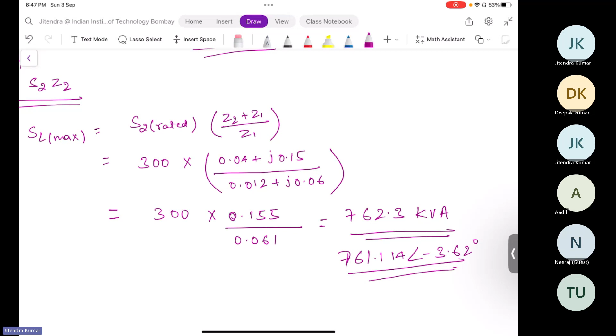If we exceed this value, then one transformer will get overloaded. Yeah, you are perfectly correct. But specifically in this case, transformer 2 will be overloaded, because we considered the 300 kVA rating since S2Z2 was less than S1Z1.